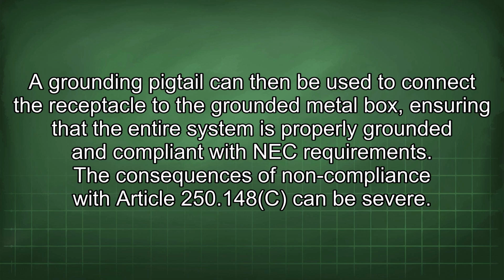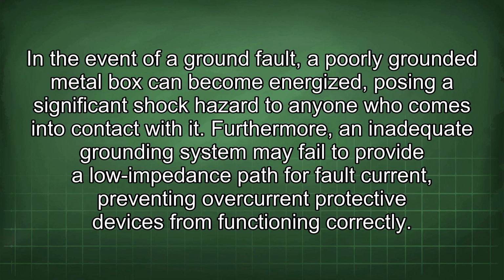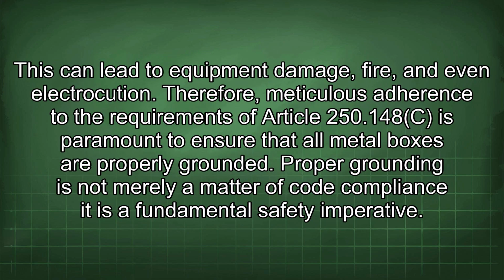The consequences of non-compliance with Article 250.148(C) can be severe. In the event of a ground fault, a poorly grounded metal box can become energized, posing a significant shock hazard to anyone who comes into contact with it. Furthermore, an inadequate grounding system may fail to provide a low impedance path for fault current, preventing overcurrent protective devices from functioning correctly. This can lead to equipment damage, fire, and even electrocution.